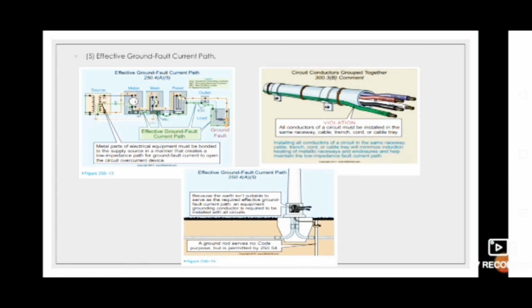Effective ground fault current path. Metal parts of electrical raceways, cables, enclosures and equipment must be bonded together and to the supply source in a manner that creates a low impedance path for ground fault current that facilitates the operation of the circuit overcurrent protection device. To ensure a low impedance ground fault current path, all circuit conductors must be grouped together in the same raceway, cable or trench. We can see from the picture, all the cables are grouped together.